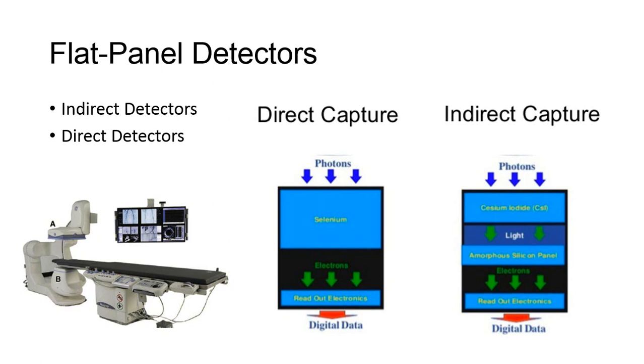Image intensifier tubes are being replaced by flat panel digital detectors capable of recording live images. There are two types of flat panel detectors available today. Indirect detectors utilize a cesium iodide phosphor coupled to an active matrix array of amorphous silicon thin film transistors. This requires an additional conversion of energy compared to the direct detector, which uses amorphous selenium thin film transistors.